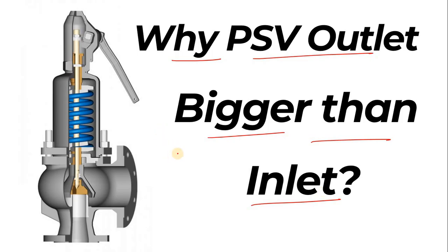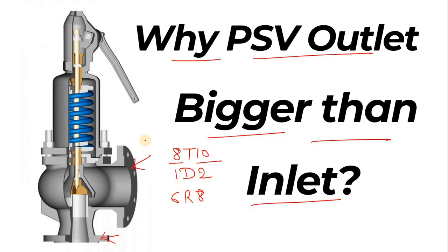The sizes are mentioned like '8 T 10' or '1 D 2' or '6 R 8'. The first number, for example 8, is the inlet size — the inlet flange size. The second number, for example 10, is the outlet size. And the letter in between, like 'P', defines the orifice size as per API.